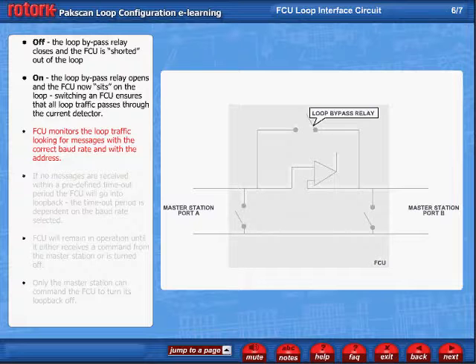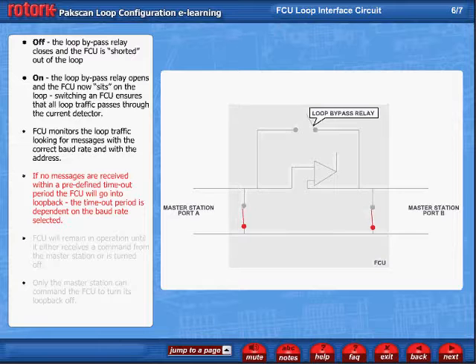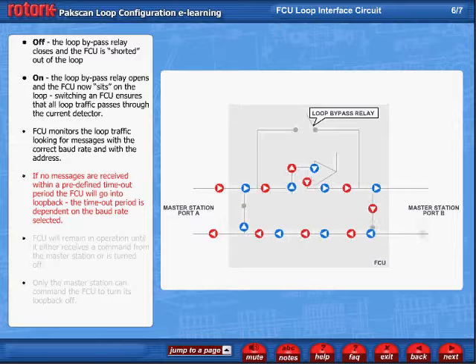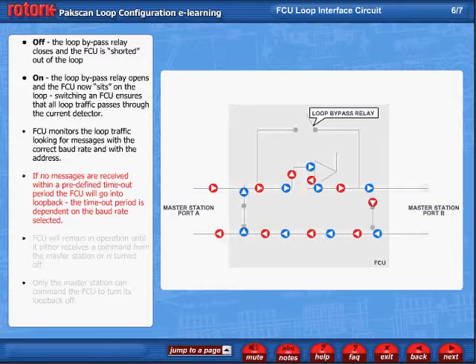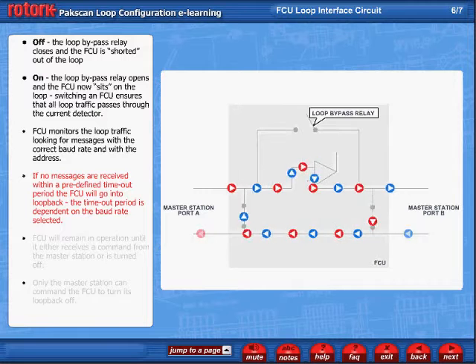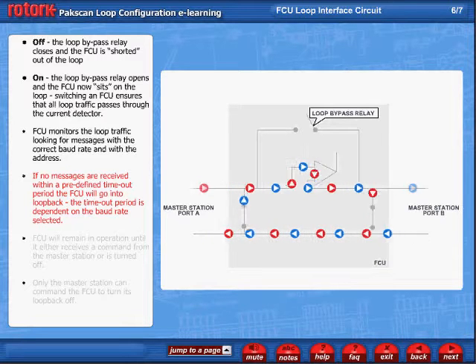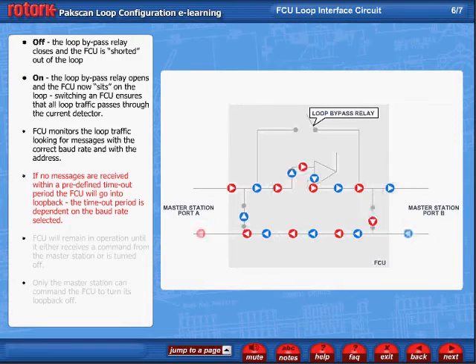The FCU monitors the loop traffic looking for messages designated for it — in other words, any messages with the correct baud rate and with the correct address. If no correct messages are received within a predefined timeout period, the FCU will go into loopback, with the timeout period dependent on the baud rate selected.